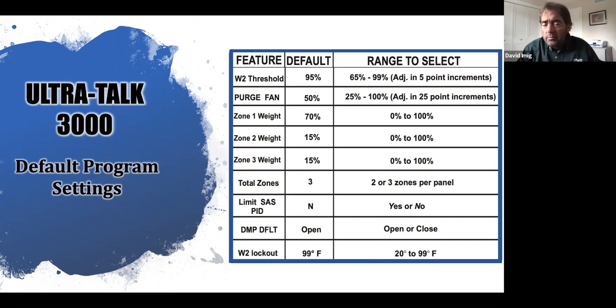Then I get to my weight features. Again, this is part of the operation, but this gives me the ability to weight my zones based on the demand and or size of that zone. It's a combination. The more demand, the larger that zone is, the heavier weight I'm going to need. That gives the zone panel itself the ability to supply less or more firing rate to satisfy calls in those areas. We'll get into that in a bit. The total zones: am I a 2-zone or 3-zone? Then, limit my supply air sensor.